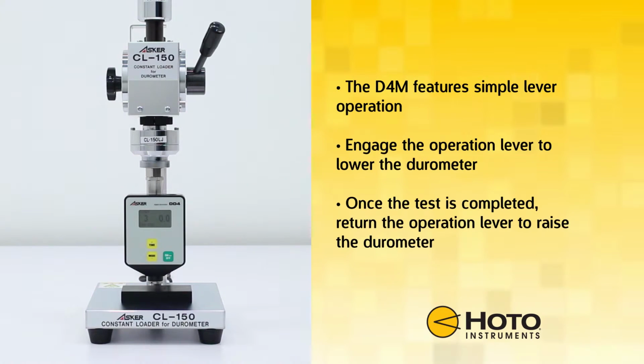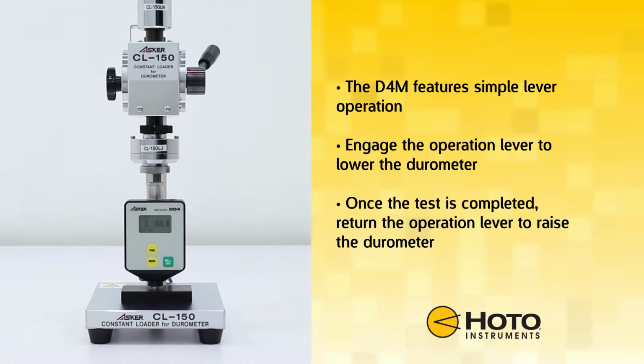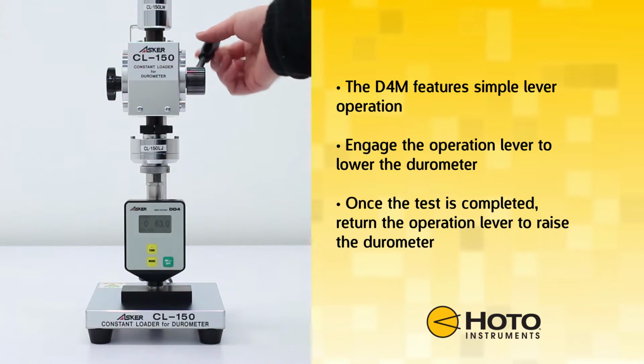The D4M features simple lever operation. Press the operation lever forward to lower the durometer. Once the test is completed, pull the operation lever to raise the durometer back to the starting position.